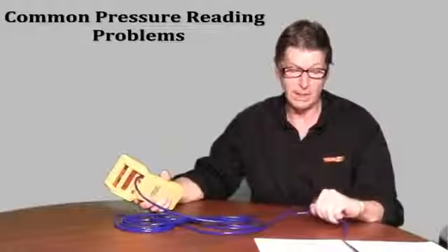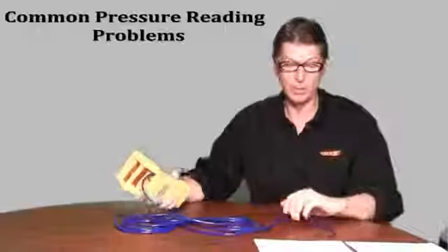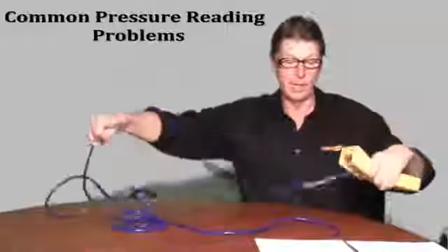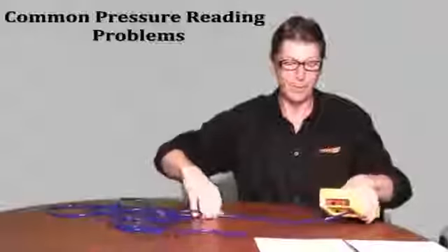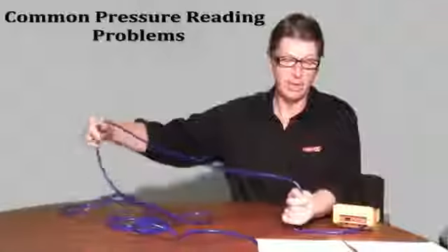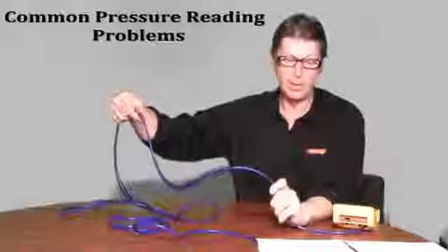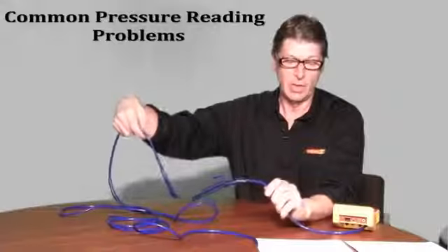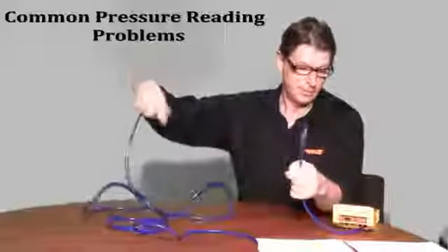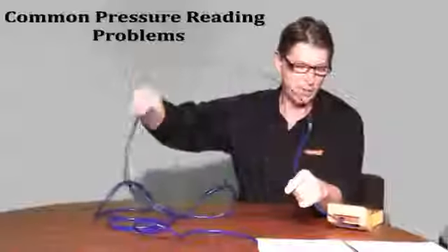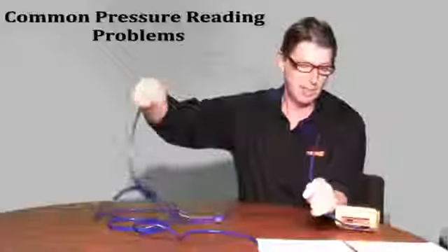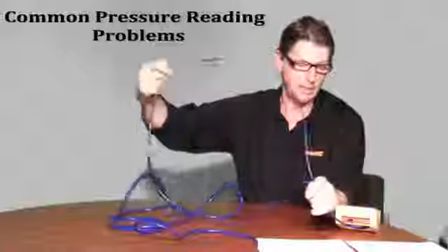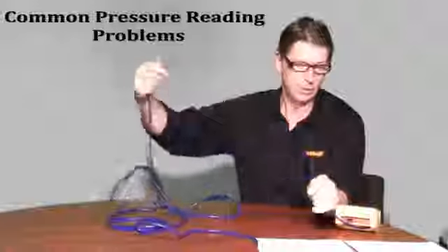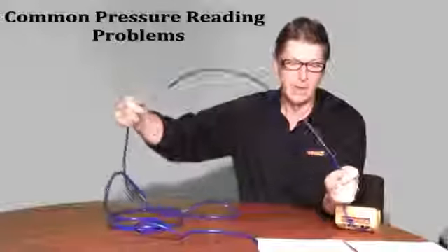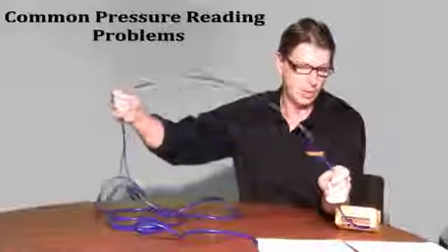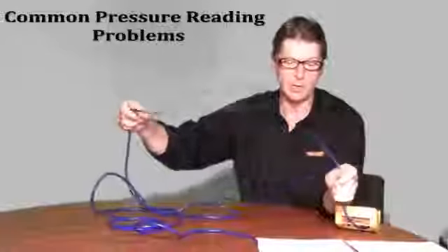In order to simulate the effect of an unsupported tube, we're going to shake the middle of this tube back and forth about a foot and see what the effect is on channel A. We want to see how much variation we get between the maximum positive and the maximum negative pressure. Do that for about 10 seconds or so while watching the gauge, and mark down your closest answer.